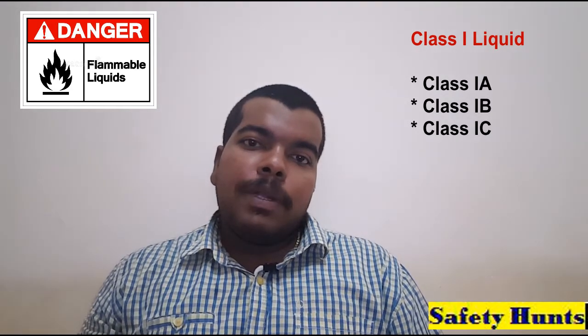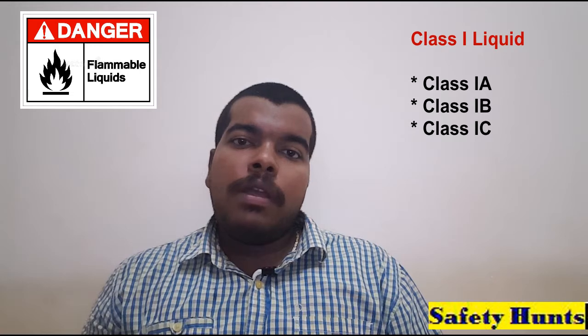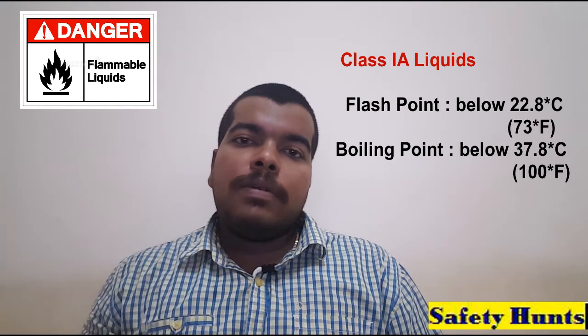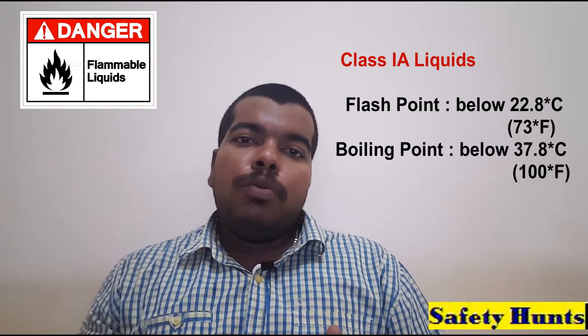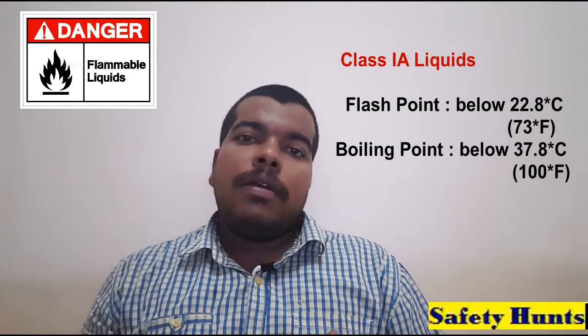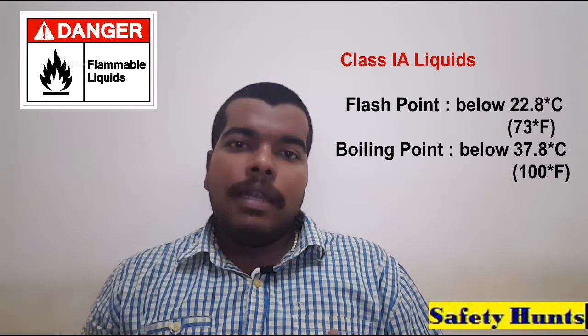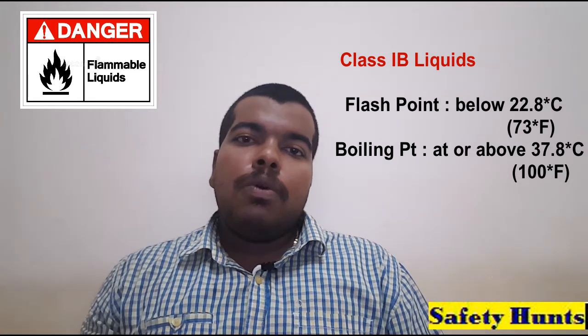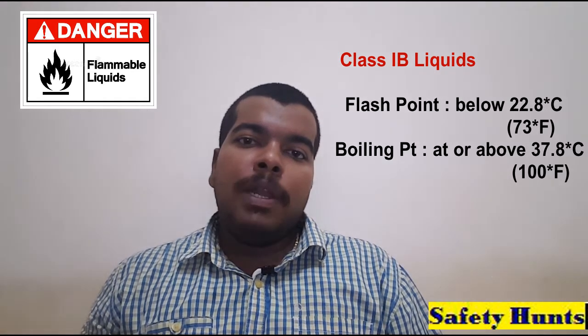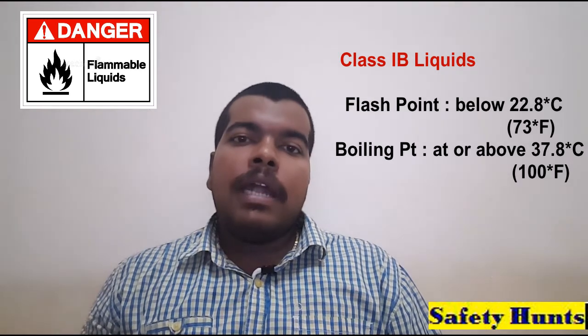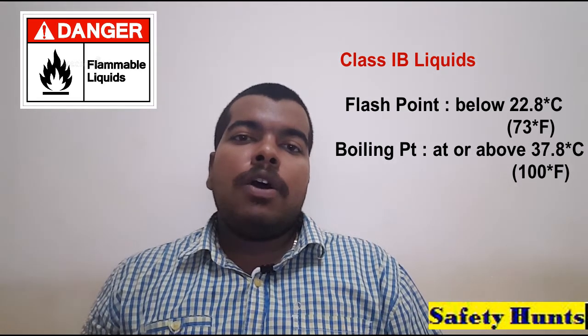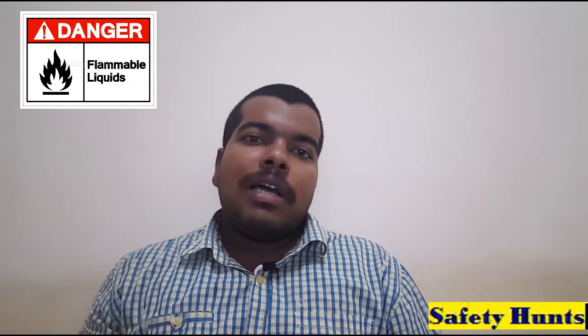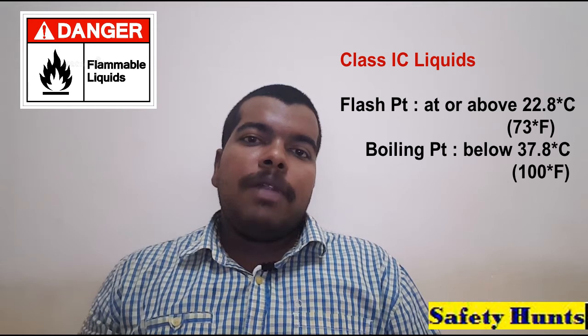Class 1 liquids can be further subdivided into Class 1A, 1B, and 1C. Class 1A liquids have a flash point below 22.8 degrees Celsius and a boiling point below 37.8 degrees Celsius. Class 1B liquids are those having a flash point below 22.8 degrees Celsius and a boiling point at or above 37.8 degrees Celsius.